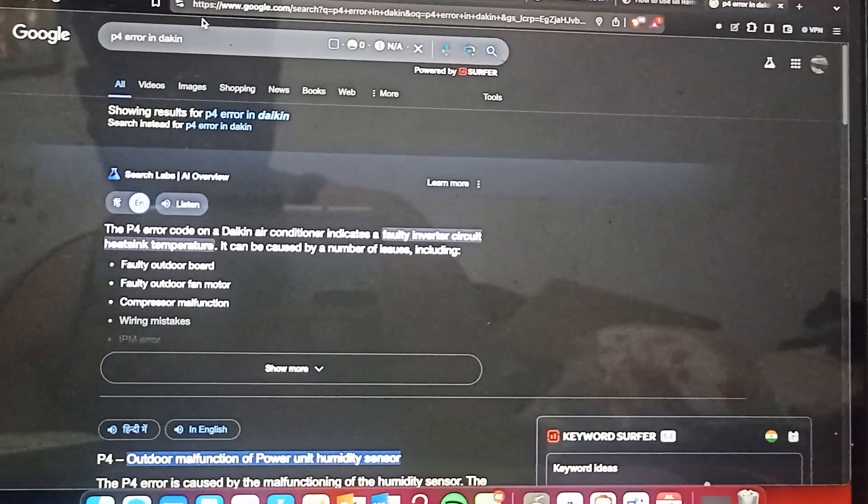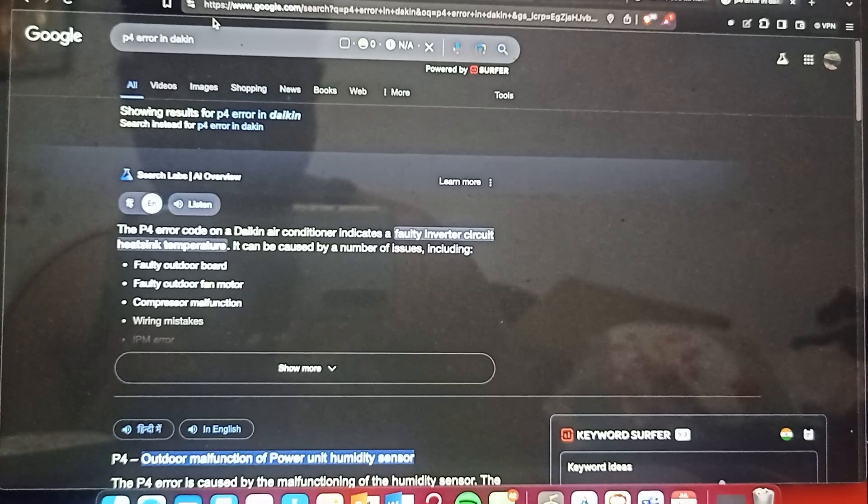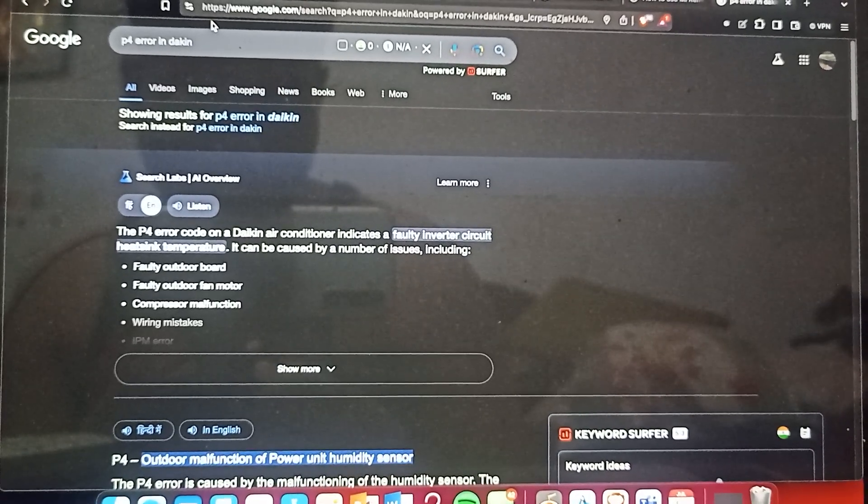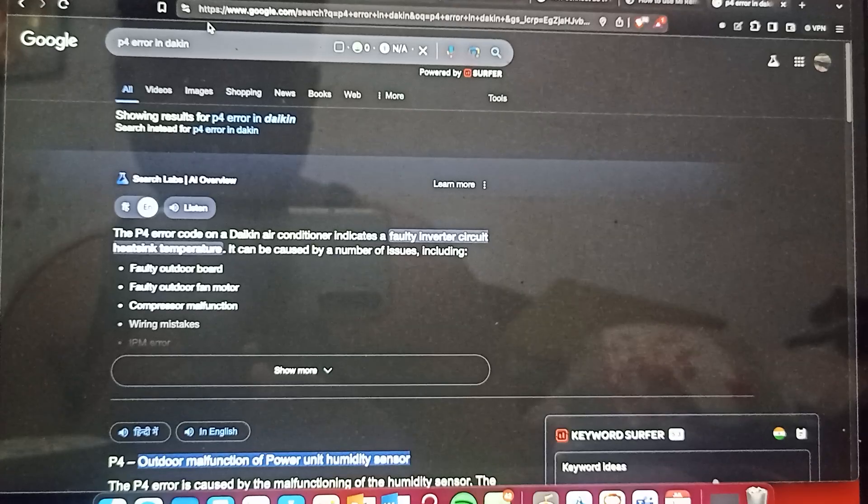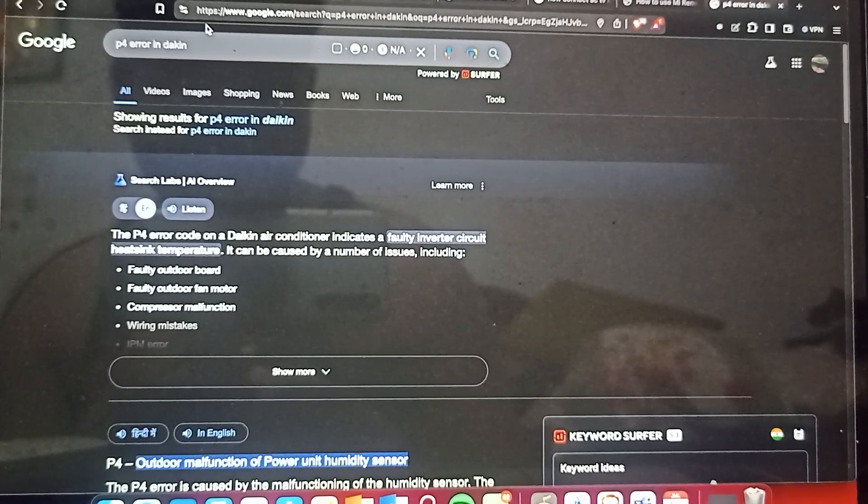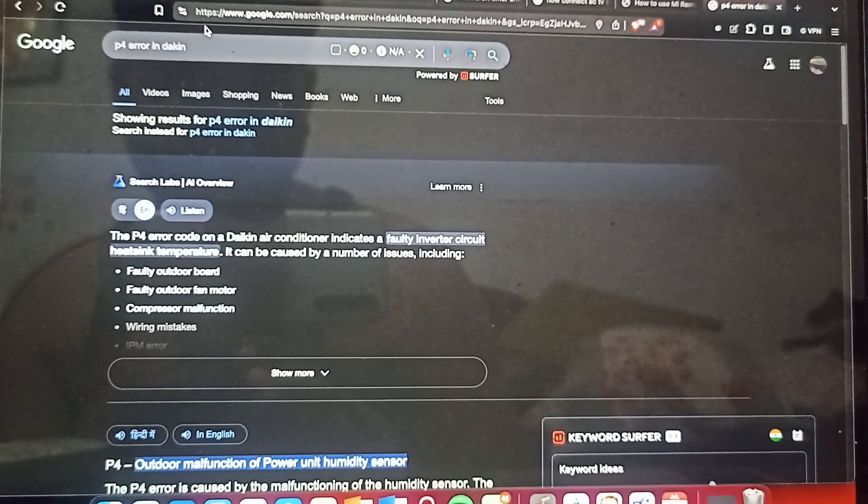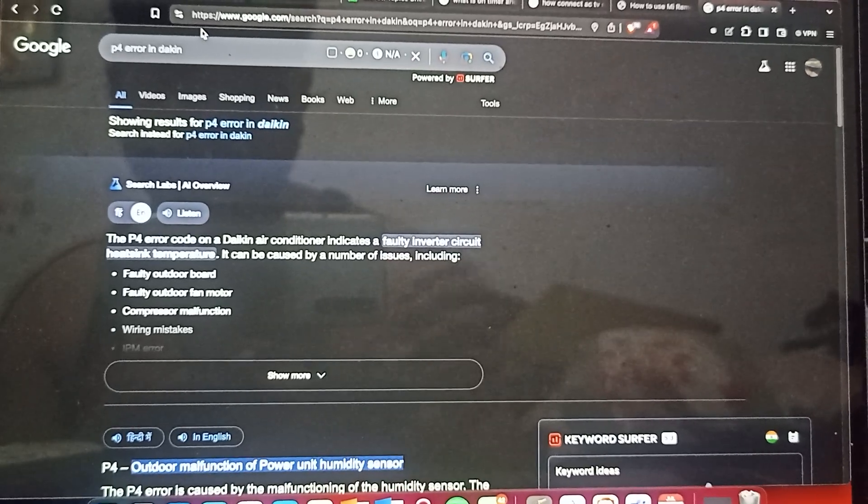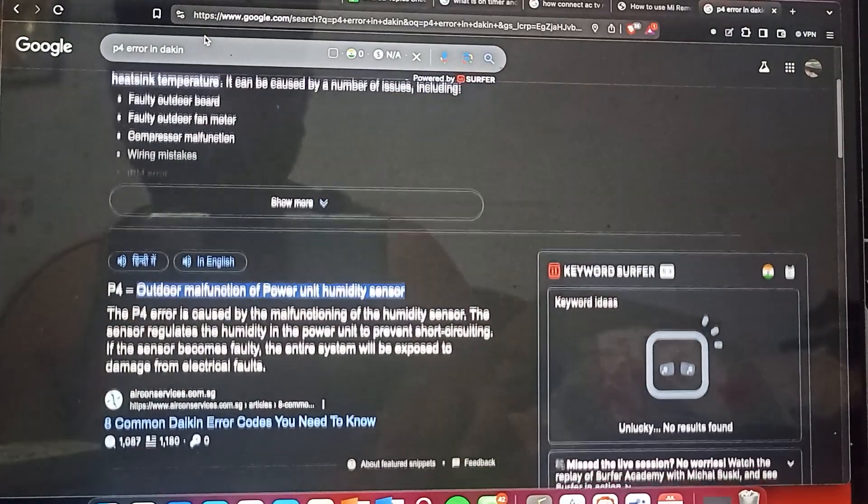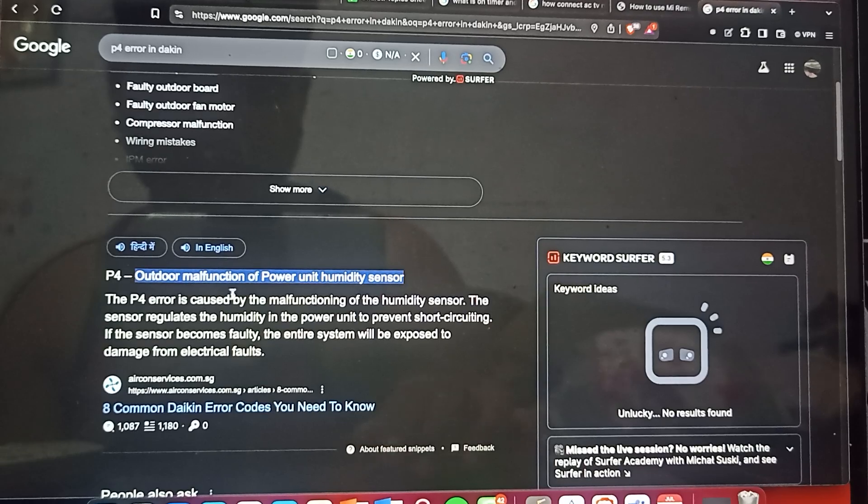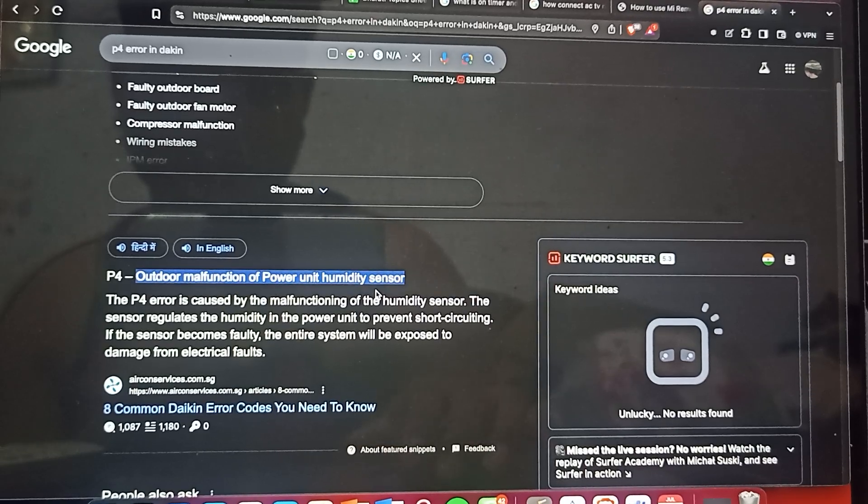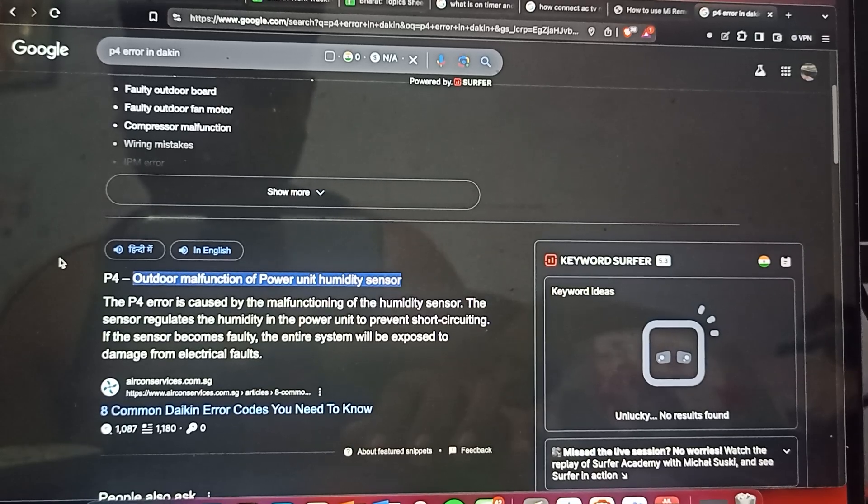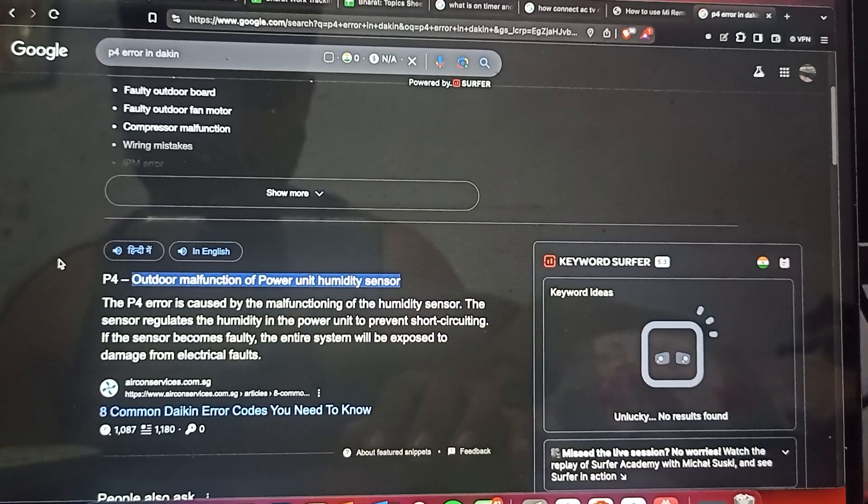You can see the P4 error on Daikin air conditioner: a faulty inverter circuit heatsink temperature. It's caused by a number of issues like faulty outdoor unit, faulty fan motor and compressor, and many more things like outdoor malfunction of power unit and humidity sensor. You can check these.